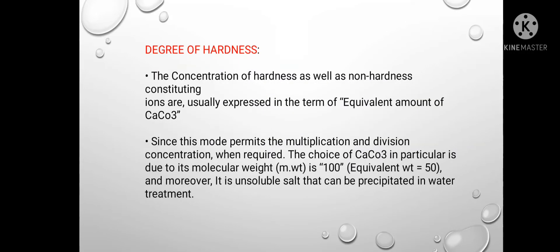Now we will see degree of hardness. The concentration of hardness as well as non-hardness constituting ions is usually expressed in terms of equivalent amount of calcium carbonate (CaCO₃). This mode permits multiplication and division of concentrations when required. CaCO₃ is chosen in particular because its molecular weight M is 100 and equivalent weight equals 50, and moreover it is an insoluble salt that can be precipitated in water treatment.